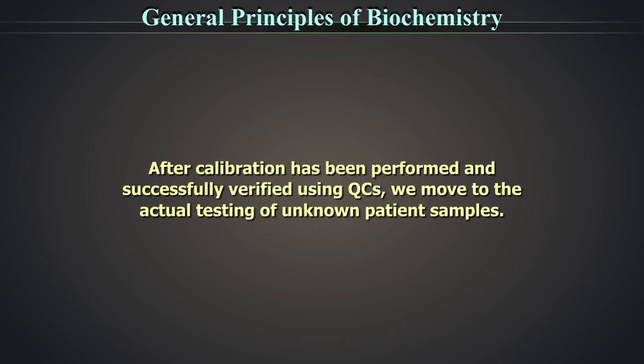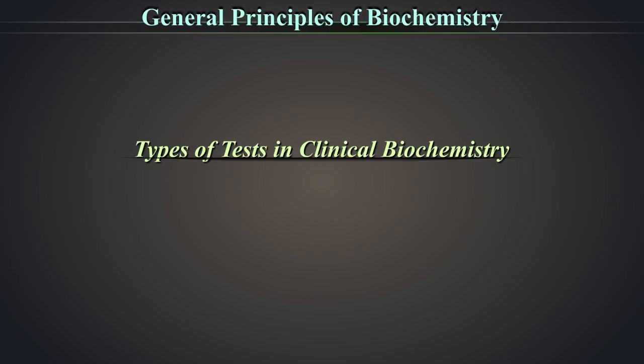After calibration has been performed and successfully verified using QCs, we move to the actual testing of unknown patient samples. There are three main kinds of tests we generally do on these analyzers: endpoint tests, rate or fixed time tests, and kinetic tests. We will discuss one test of each kind in this tutorial. We will take up the principle of each as we get there.